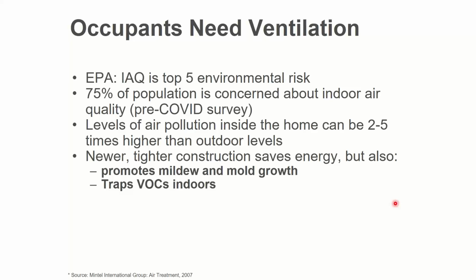And if I bring more air into my building, other air has to leave. Right? It's not like I suck air into the building and then it just keeps blowing up like a balloon and expanding and then my walls bust open. It doesn't work like that. If I bring 1,000 CFM of fresh air in, somewhere else 1,000 CFM of bad air has to leave. And that's what I want to do. I want to intentionally bring fresh air in, and I want to have targeted places where I bring air out. So I always have an air exchange of fresh air.